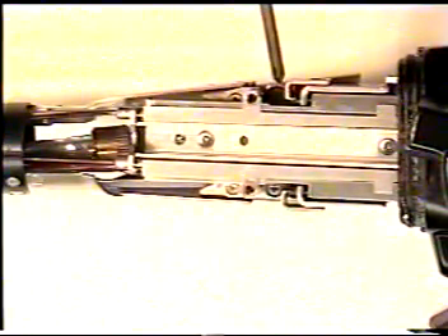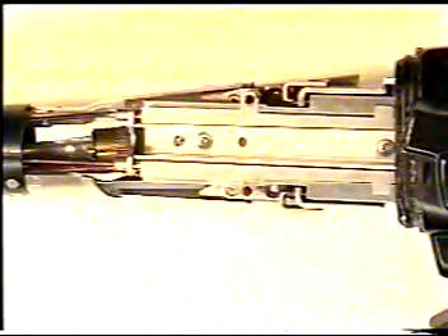Unscrew 2 Phillips screws which hold down the angulation control block. There is 1 screw on top and 1 on the underneath side. Carefully turn over the instrument. This is the most critical part concerning this repair, so as not to damage light bundles and/or image bundle or video cable. Carefully locate the Phillips screw on the underside of the control block by pushing away, if necessary, air-water channels, and unscrew the Phillips screw.